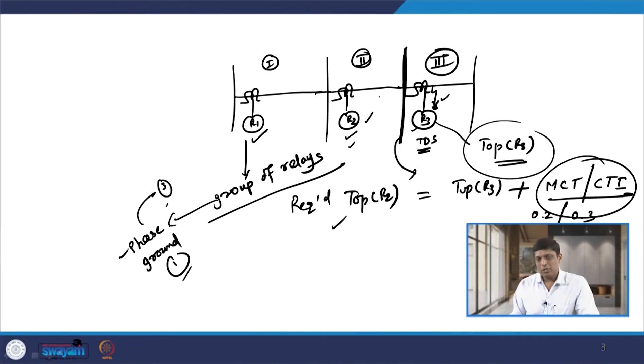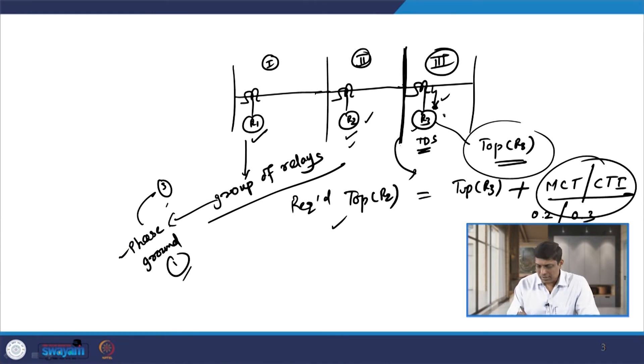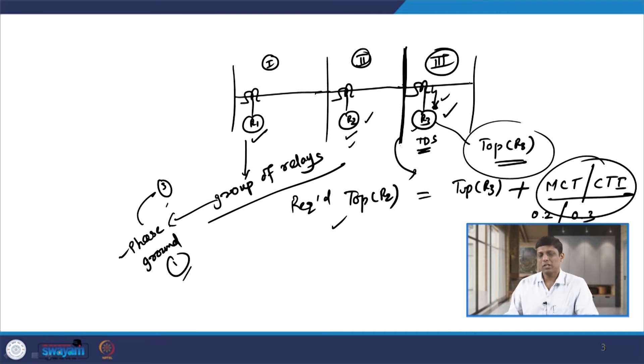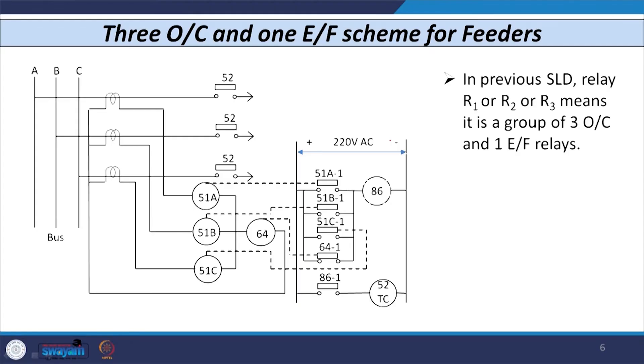R2 also means a group of relays — it has three phase relays and one ground relay. Similarly, R3 is also a group of relays: three overcurrent and one ground relay. If I consider the network, we have three conductors R, Y, B (or A, B, C) and a relay connected in each phase — so 51A in R phase, 51B in Y phase, and 51C in B phase.